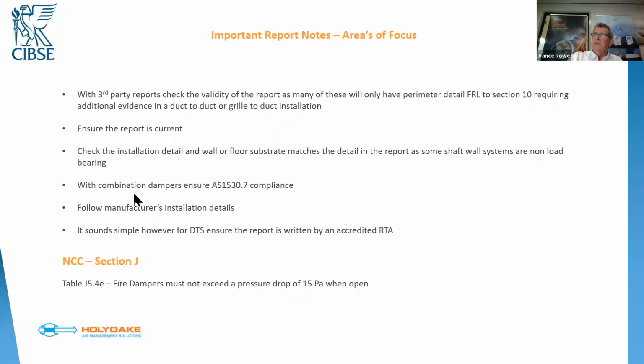All right. Now, just very quickly, finishing up, third-party reports. There's one out there, for example, from Speed Panel that's got ours and a number of other manufacturers' material in it. If you read through that report, even though it uses the term duct connected to penetrations, you'll find that when you look at the detail, all it does is assess the perimeter seal in a Speed Panel wall. So if you were to check the validity of a fire damper in that Speed Panel wall, you actually need our report as well, so that you can assess whether the fire damper was tested to section 11 or not, because that particular Speed Panel report is really only dealing with a section 10 test on the perimeter seal.